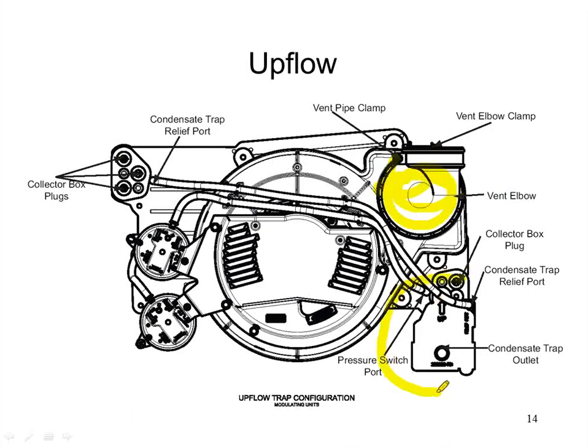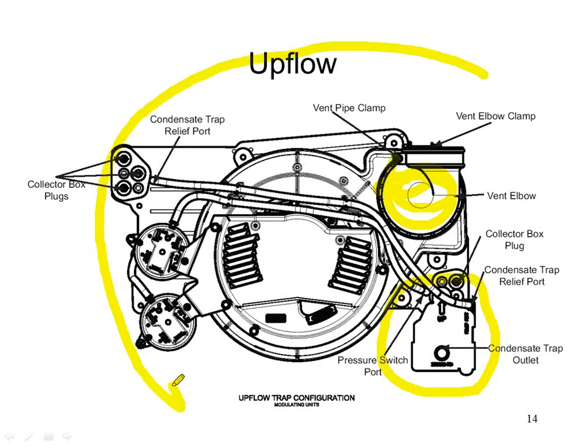Another thing I got to pay attention to is the condensate trap. This is where all the water is going to eventually collect and dump into before it goes out the PVC pipe and drain away. I can't have that condensate trap on the top side, obviously, because water will not flow upward. So if I flip this whole entire furnace 180 degrees, now this condensate trap is going to be over here on the top left side. So I have to actually move him.